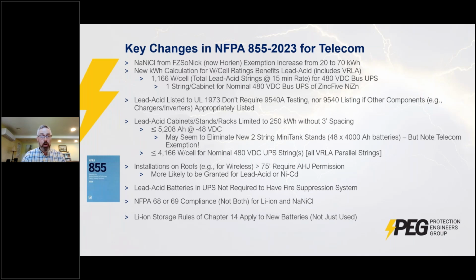So they don't want very large fires, and they don't want fires to spread from one rack or stack of batteries to an adjacent stack. So they limit, in general, the size of the battery stack or module (we call it strings, they call it a module) to 50 kilowatt hours. And between every 50 kilowatt hour stack of batteries, you need to have a 3-foot spacing.